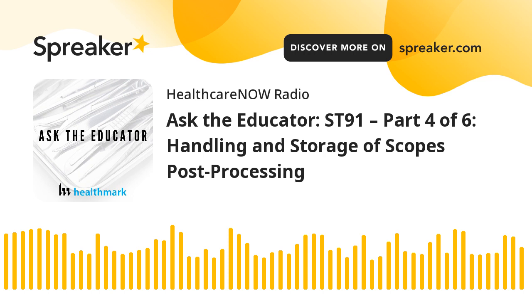The other thing to reinforce—and this isn't anything new, it's been in other standards and guidelines before—is no endoscope storage in a procedure room. Ideally it would not be in the processing room unless you have a complete dirty-to-clean flow in a one-room processing room, and then it would be at the very cleanest end of that space. The preference is that it's in its own clean storage room. I'm sure all of us have seen places where we had clean or processed endoscopes right there in the procedure room.